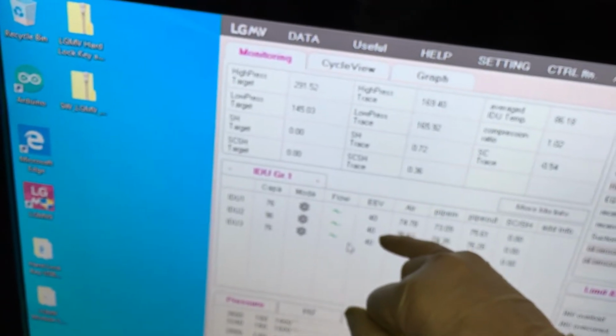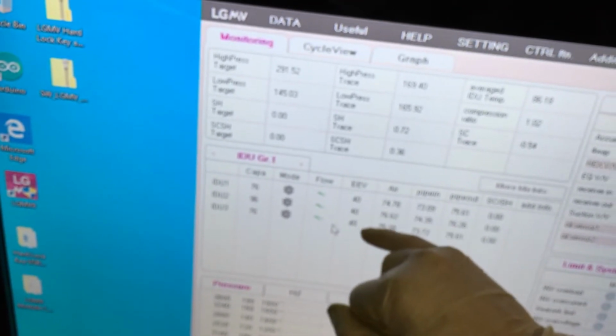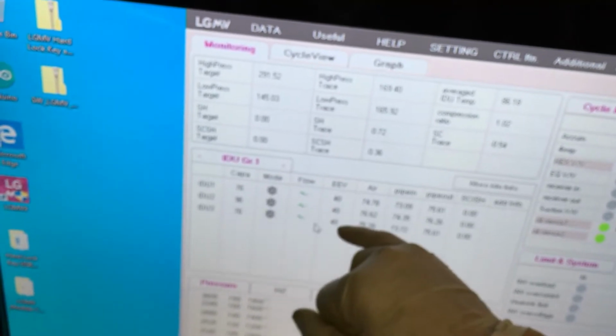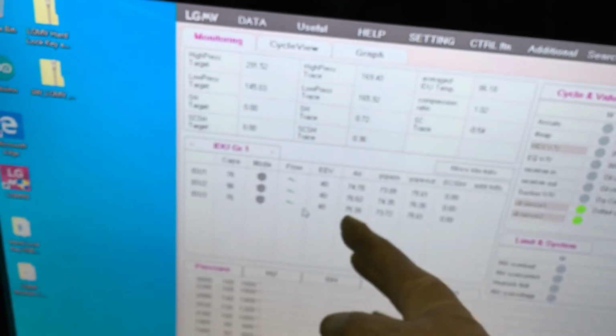And so this is like a little extra measure over your normal everyday logging or waiting for a problem happening. You actually can see when something is drifting out. If you always noticed, like if this system came on right now and you always noticed that two of the expansion valves, their duty cycle was say at 350 and one was still staying at 40, and it was always staying at 40, but it was enough that it worked, but it didn't set an alarm. You go, okay, for some reason this one's not working.